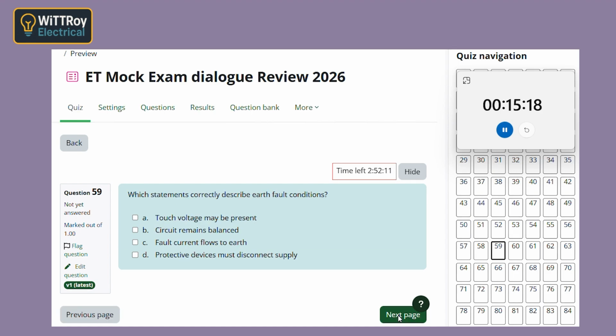Question 59. Earth fault conditions. Fault current flows to Earth? Yes. An earth fault means current leaves the intended path and goes to earth or to exposed conductive parts connected to earth. So touch voltage may be present because metal parts can rise above earth potential. Correct. That's the danger. If a person touches a live faulty metal part and earth, current may pass through the body. So protective devices must disconnect supply. Exactly. That is the purpose of earthing and protection working together.